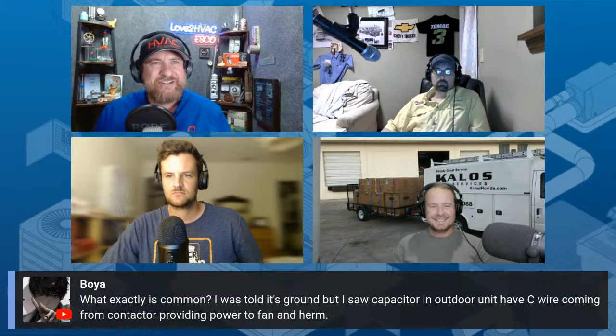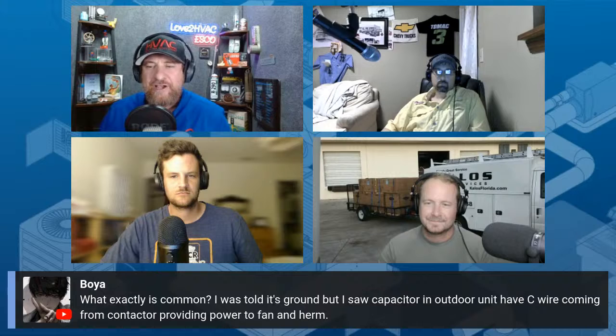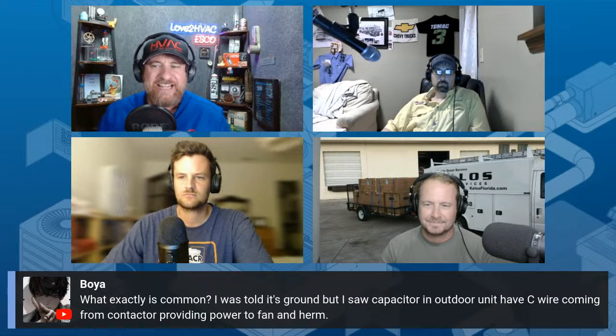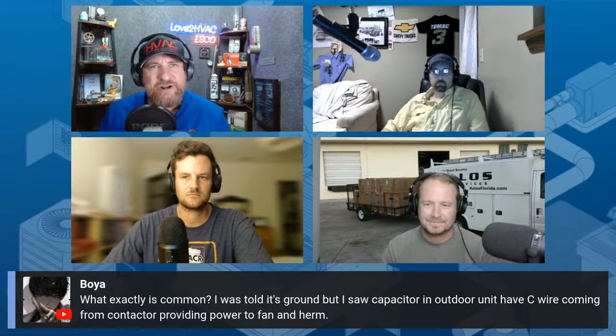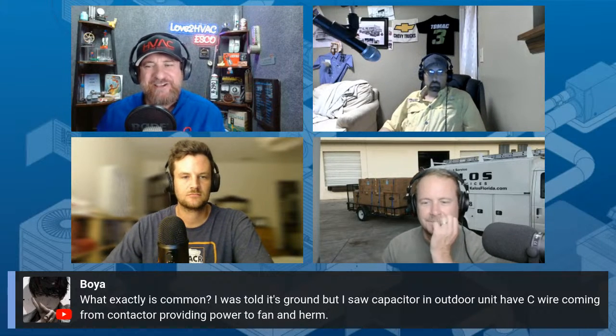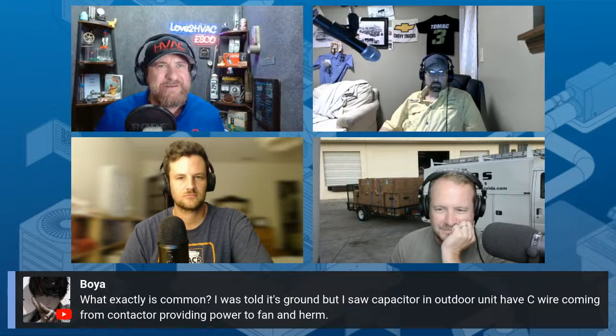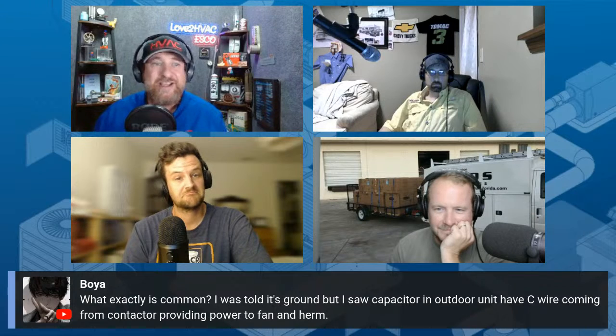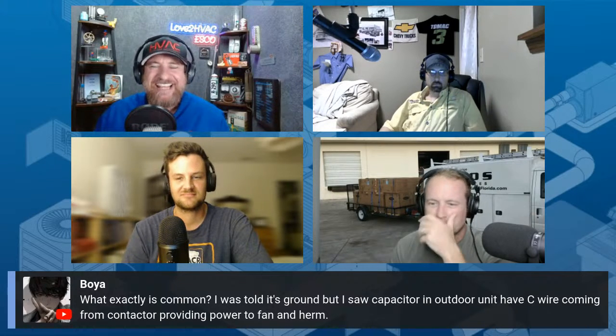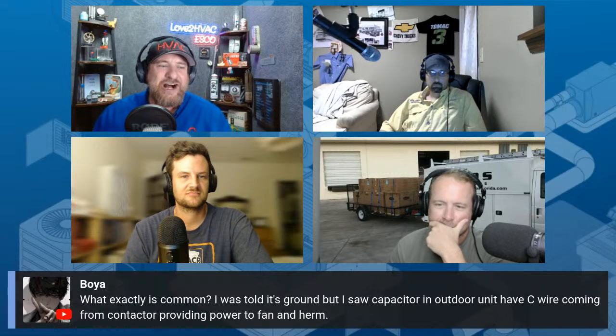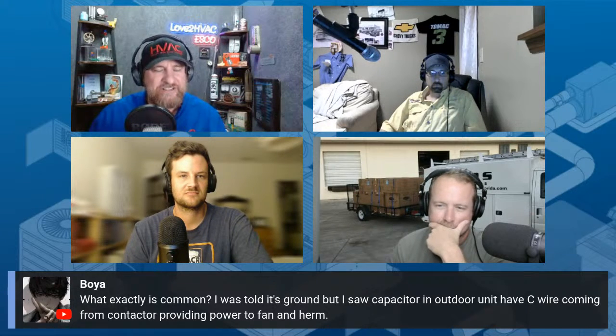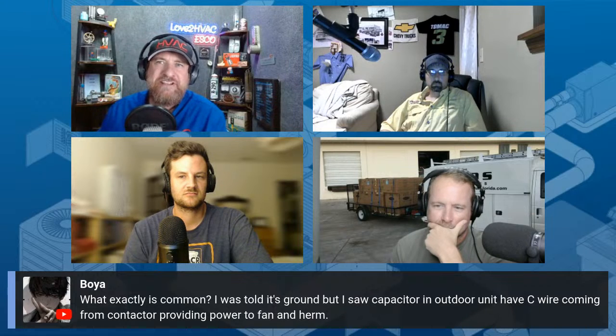If you look at a capacitor, there's a terminal that's being shared. There's a dual run, so there's two capacitors in there, and one of those terminals is shared. So that capacitor has something in common. A compressor has a run winding and a start winding. Instead of having 4 wires coming back from the compressor, they just share one terminal, so the compressor has something in common, but it's opposite of the common of the capacitor. Just because it's a C terminal doesn't mean it gets along. Then you have common for a transformer, which is a completely different voltage and a separate circuit from all the other commons. So common just means of that component or that one circuit, not that all the commons go together. It's certainly different from ground.